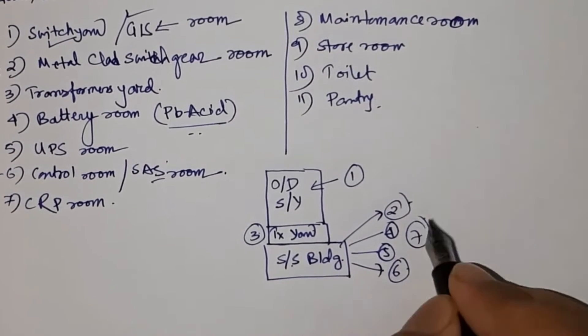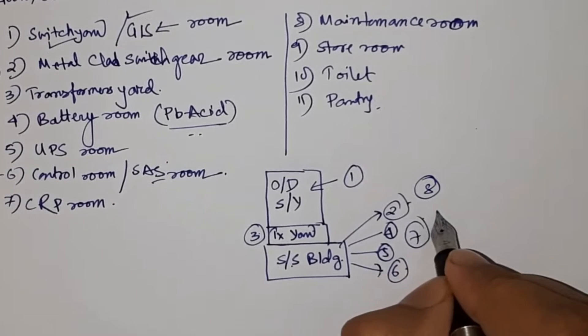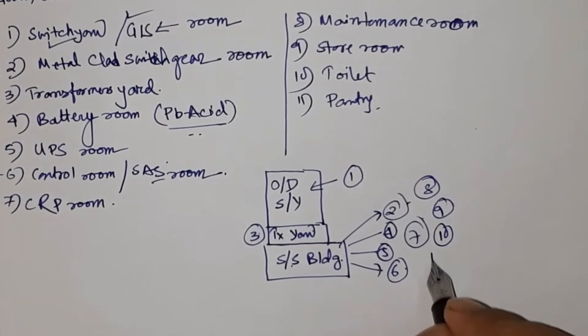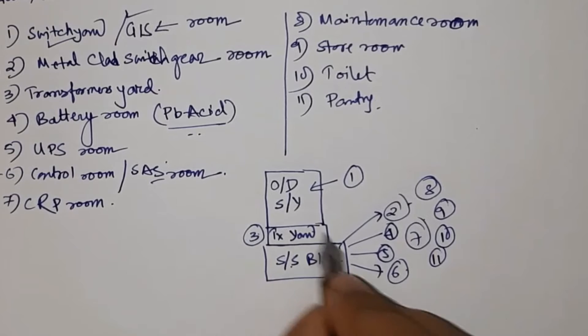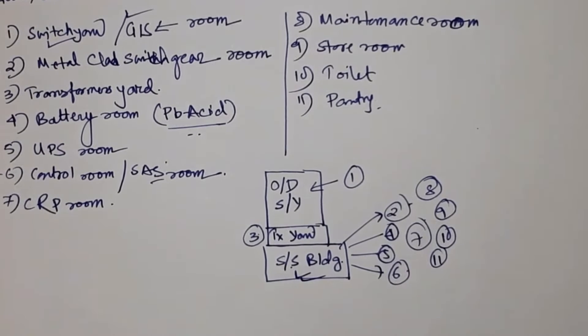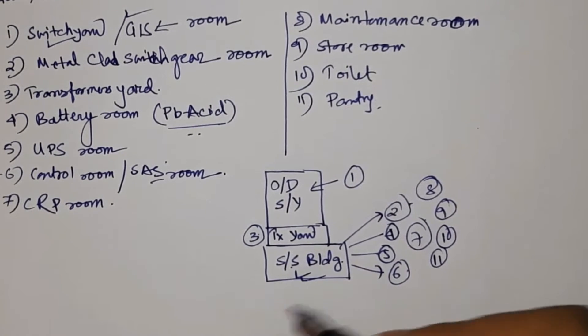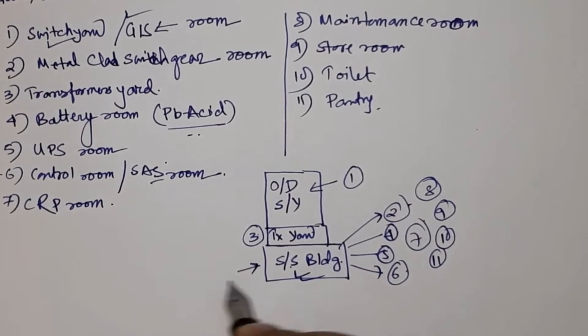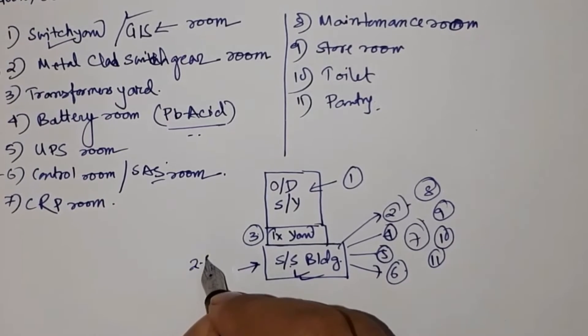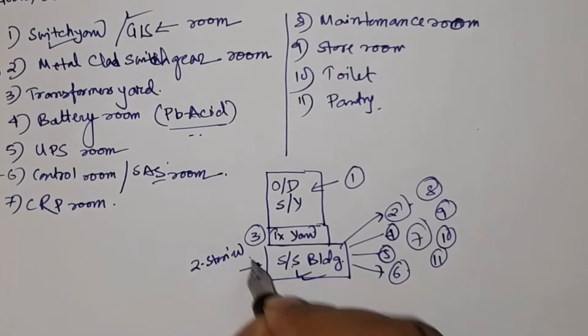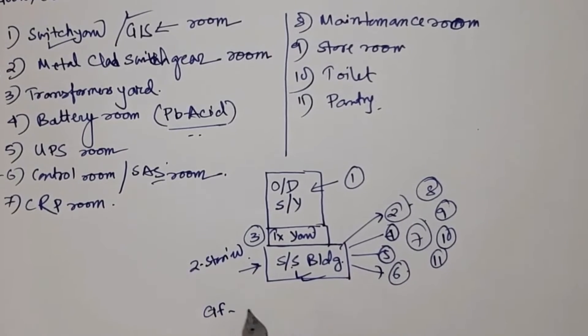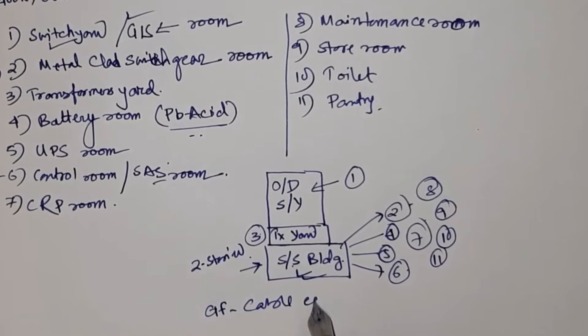The CRP room, maintenance room, store room, toilet, pantry, and so on — all these will be housed inside this substation building. You have to make the layout in such a way as to accommodate all of these. In case there is a high cable load, you can make it a two-storied or three-storied building where the ground floor is used as a cable cellar room.